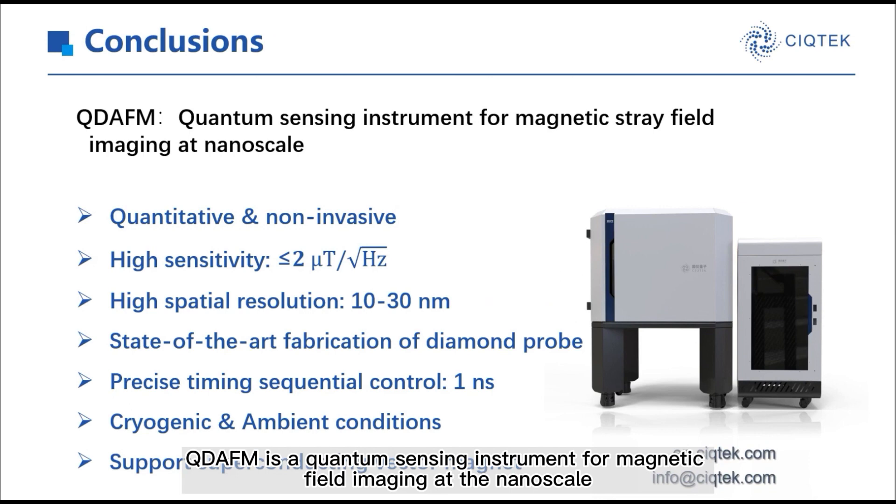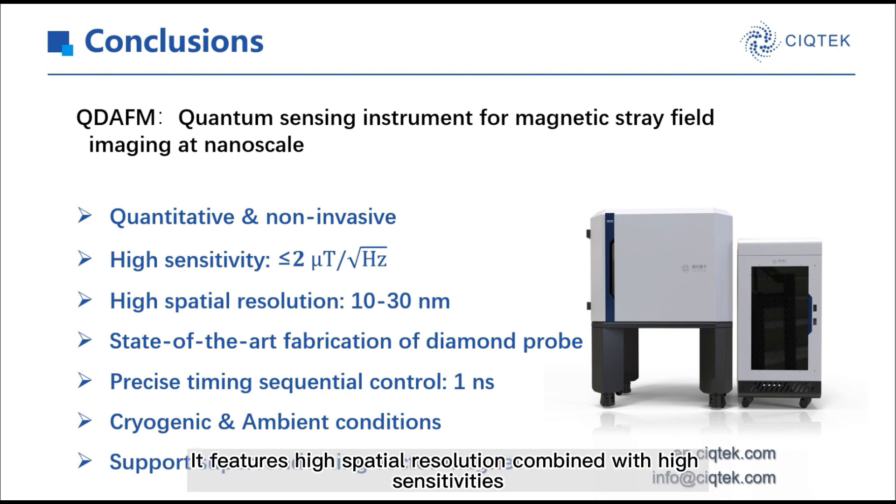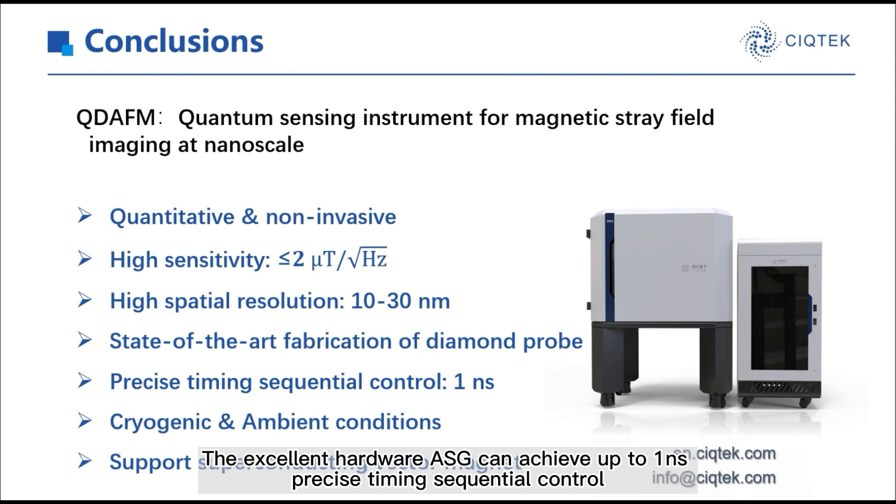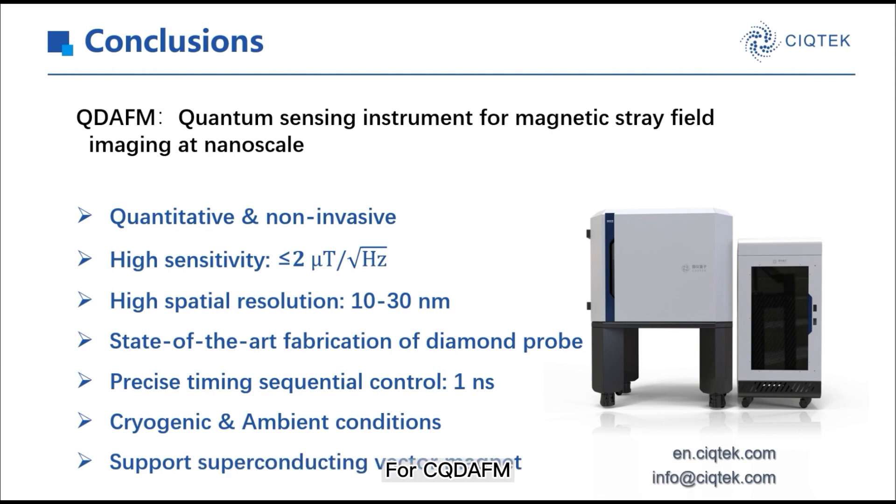In conclusion, QDAFM is a quantum sensing instrument for magnetic field imaging at the nanoscale. It features high spatial resolution combined with high sensitivity. We can offer two types of diamond probes. The excellent hardware ASG can achieve up to 1 nanosecond precision timing sequence control. For CQDAFM operating at cryogenic temperature, superconducting vector magnets are supported. This is only a brief introduction of QDAFM — if you want to know more information, you are warmly welcome to contact us at any time.